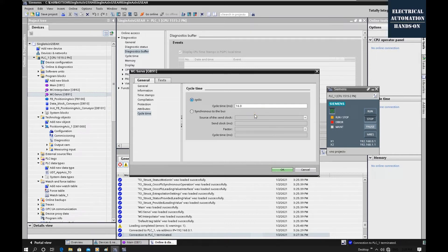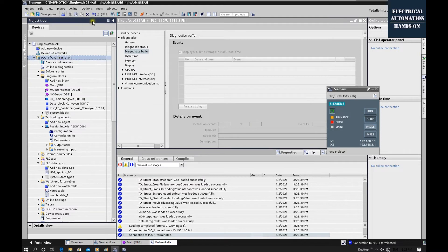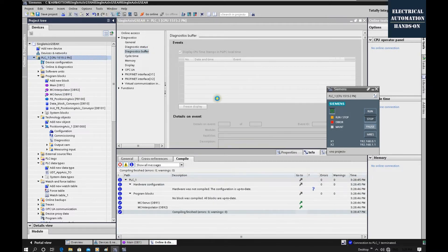If you are using actual hardware — especially Siemens SINAMICS drive systems with PROFINET IRT communication — don't forget you need to switch to synchronized-to-bus mode. You can also set the factor, and the cycle time is based on the PROFINET field bus. A shorter clock or factor means higher communication workload. Click OK, then compile — don't forget to compile — and then download.